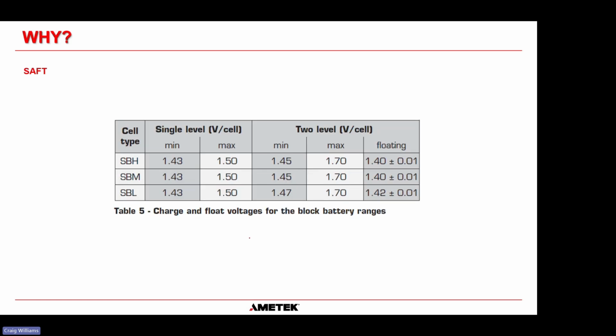Once again, why? Well, because all of the battery manufacturers tell us how to do it. So for a single level charge for the SBH type of battery from SAFT, they're saying it should be anywhere between 1.43 to 1.5 volts per cell. So if you go in the middle, it's around about 1.47. And really nobody does the 2-level charge anymore. So that's where we get those numbers from.